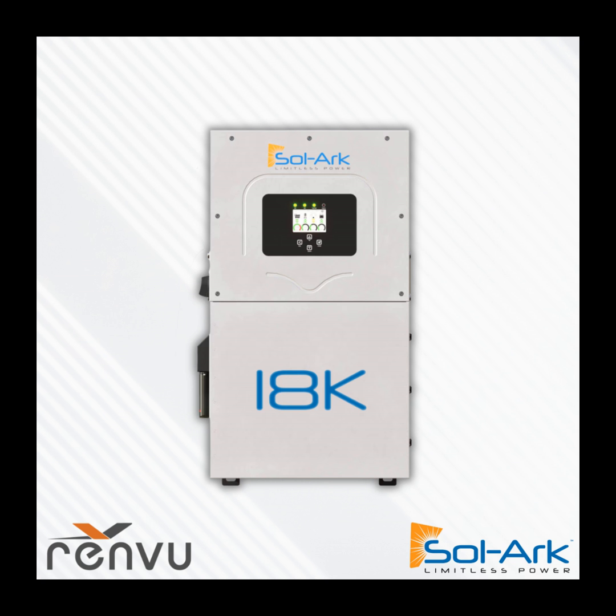It's fundamentally a larger inverter. Looking at the data sheet, the max solar array size is larger at a little over 32 kilowatts, and we can process 28 kilowatts of PV power, so very large solar arrays you don't need to worry about. If you really want to blow it out of the water, you can do DC and AC coupling simultaneously. Honestly, for off-grid systems, my opinion is that we've been oversizing the solar arrays for no reason -- in those circumstances it's better to accept a little bit of generator use rather than trying to eliminate the generator entirely. But the capacity is there if you want a large array. If you still have net metering and just want the largest solar array you can get, we're not going to stop you -- in fact, we'll help you do that. The voltage range on the MPPTs are the same.